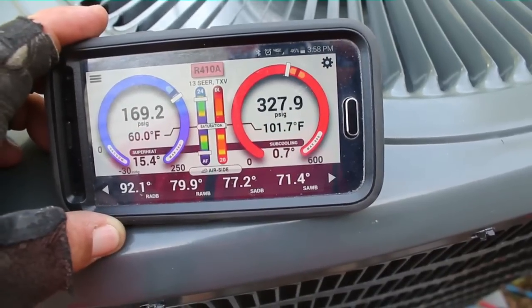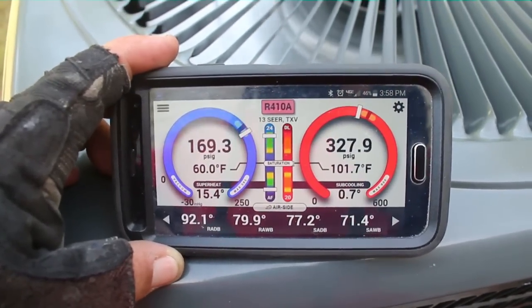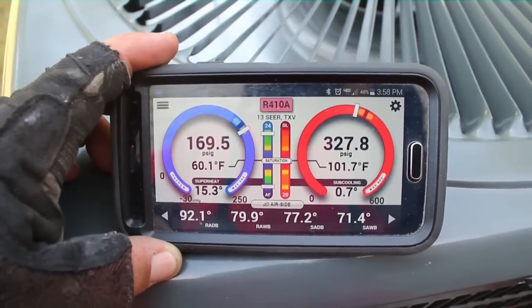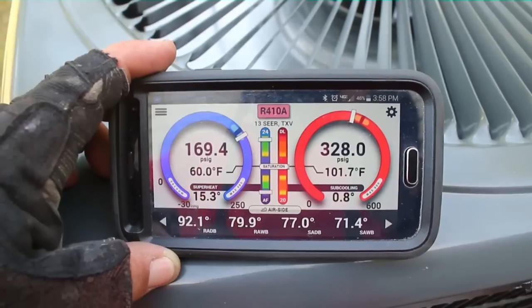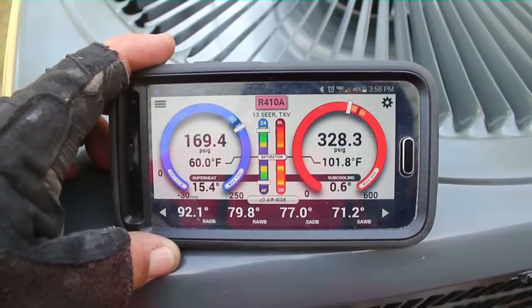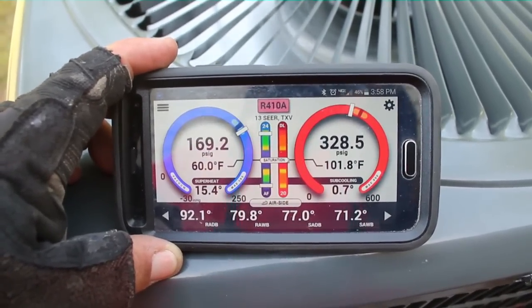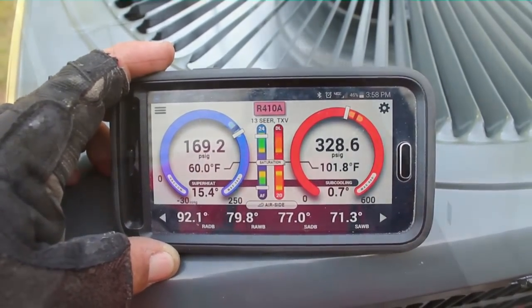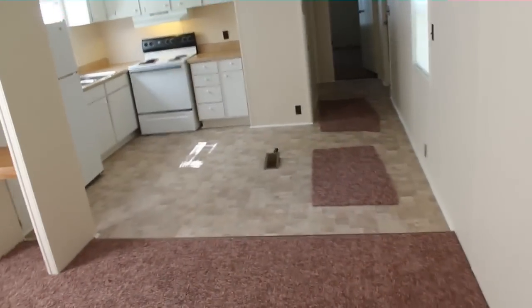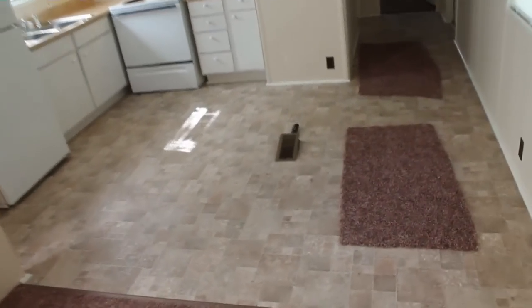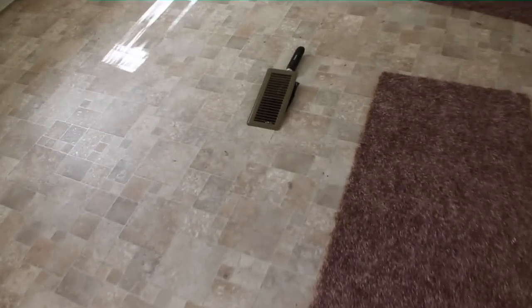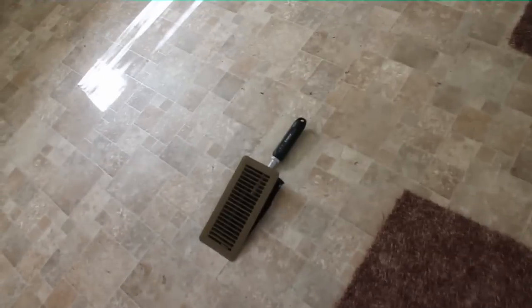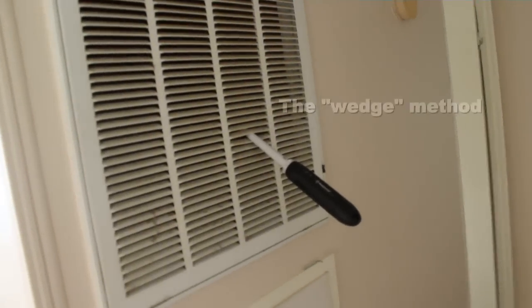As you see down here, we have 0.8 subcooling, and the head pressure is a little off because we only have just under 8 pounds of refrigerant in the machine, and it requires almost 11 according to the data plate. But we're going to pump it up with refrigerant. This is the inside of the single wide. Lieutenant's moving in tomorrow. There's our supply air probe. On the closest supply grill, we have our return air probe skillfully tucked in between the return grill fins.